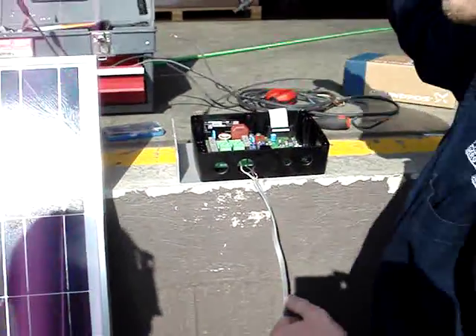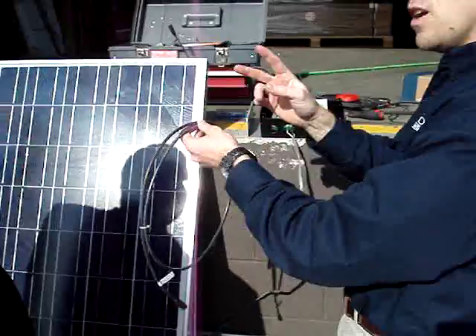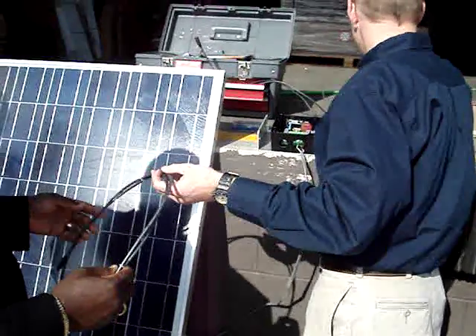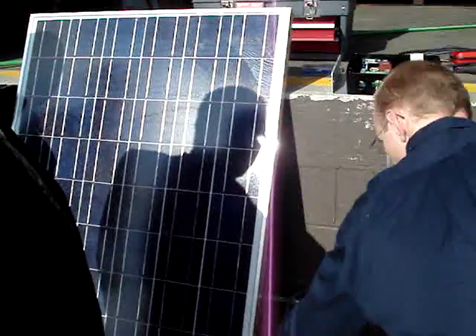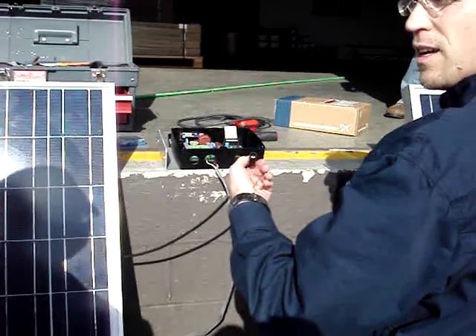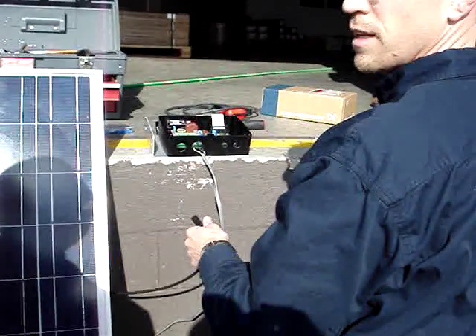You've been supplied with a cord that looks just like this — a six-foot MC connector. You're going to cut that in half. Why? Because it's going to allow us to make our connections to the panels without cutting these. We don't want to cut these because it voids the warranty on the panel. We don't want to drill any holes in the panel because it voids the warranty on the panel.